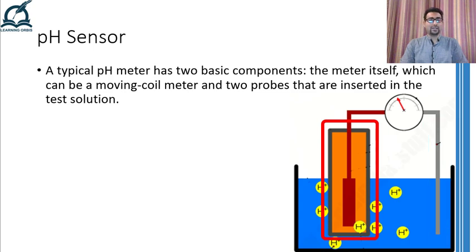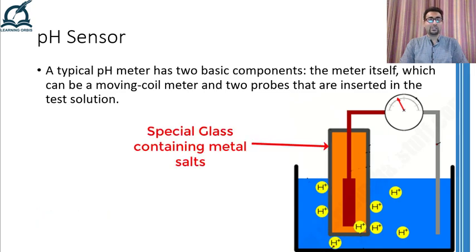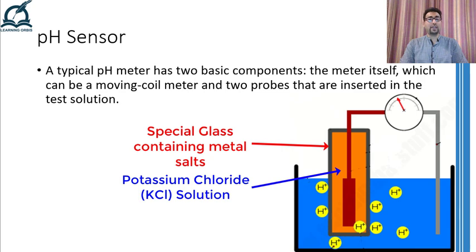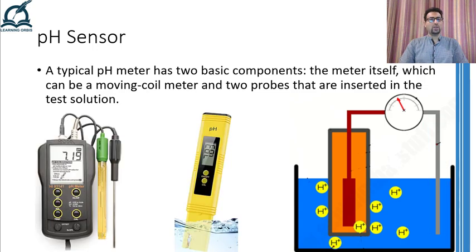One of the two probes is a glass electrode that does the main job. The glass electrode is made of special glass containing metal salts in it. Inside the glass electrode is a potassium chloride solution that has a pH value of 7. Furthermore, a silver-based wire is also present in the tube that is connected to the outside of the tube and then to the meter. The other probe is simply a silver chloride wire suspended in a potassium chloride solution. The whole device comes in two different forms: in one of them, both probes are separately provided, whereas in the other, a single housing contains both probes.